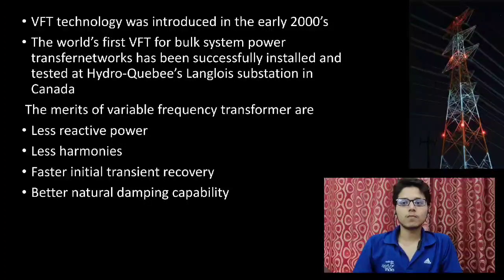VFT provides isolation between networks, it improves grid stability, meets power transfer needs during normal conditions and supports during fault conditions. So, till now we can come to a conclusion on why we are using a VFT rather than HVDC transmission. Well, that's because we have a few merits, and the merits are less reactive power, less harmonics, faster initial transient recovery, and better natural damping capability.